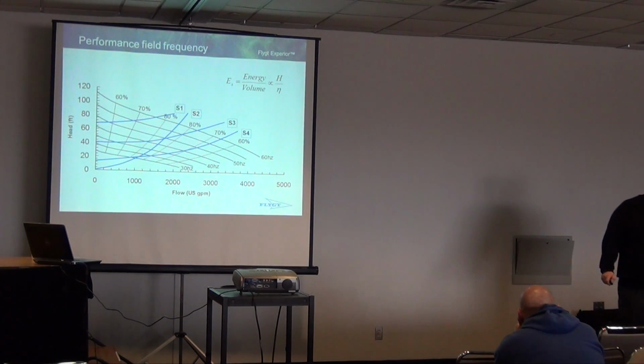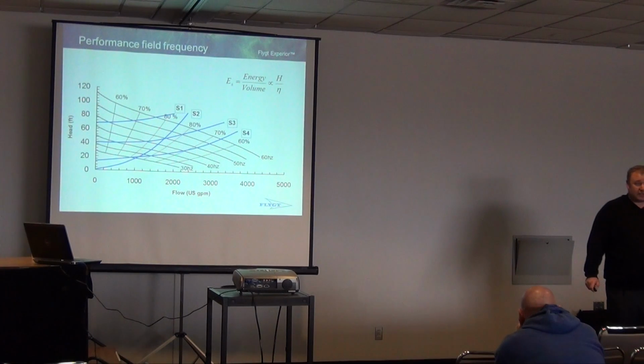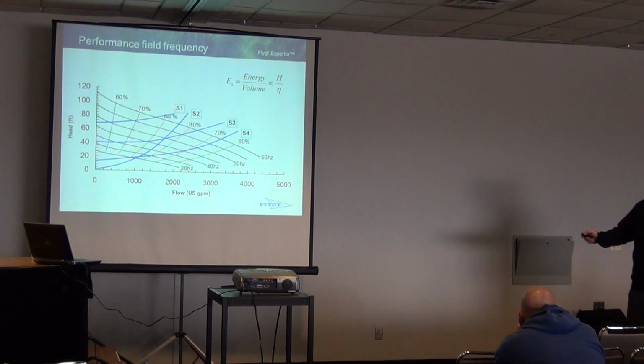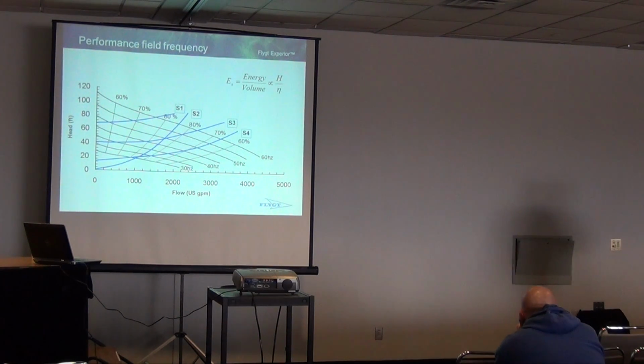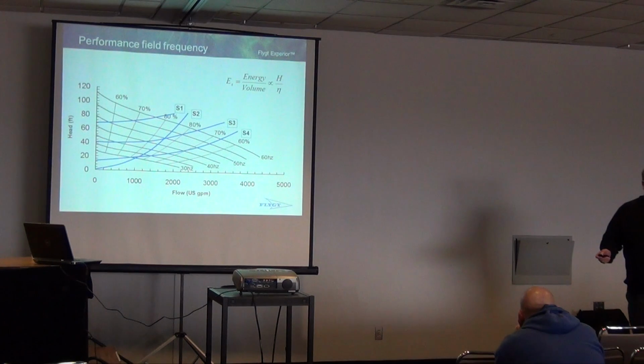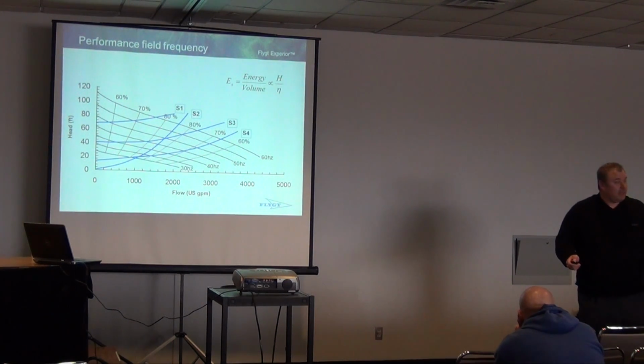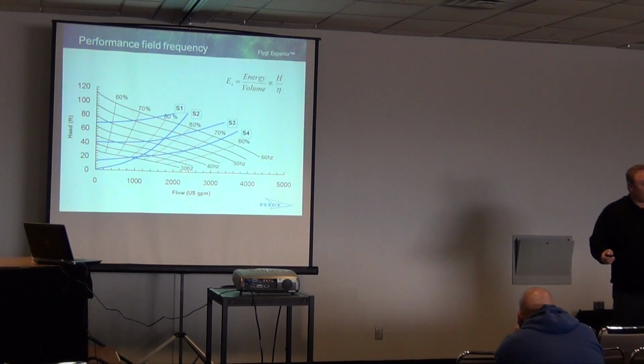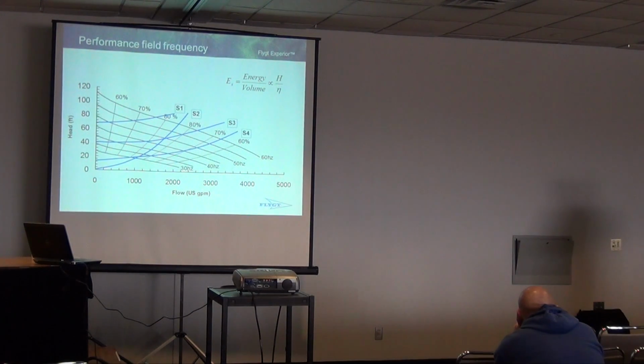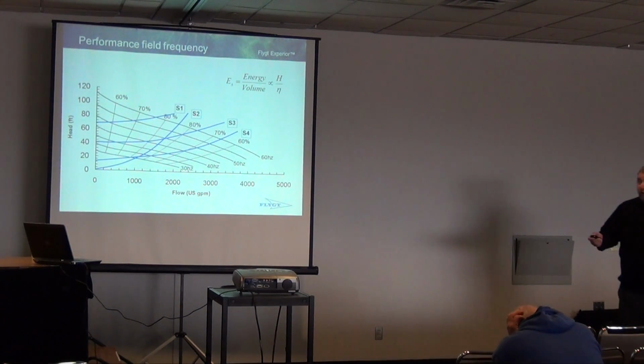As it's pushing wastewater for you on a day-to-day basis, on standard flows coming into your station, it should be able to do this. Now, I'm sure as operators you're asking, wow, if I get a lot of I&I, or a high wet weather peak flow, what does this mean? These units will recognize that inflow through the transducer. They will ramp up to full speed and they will run. When it hits a level where it's calling for the second pump, or the lag pump, where it's randomized its start, which we're going to talk about, it will ramp that one up and run both of them, just like you would in a normal duplex station.